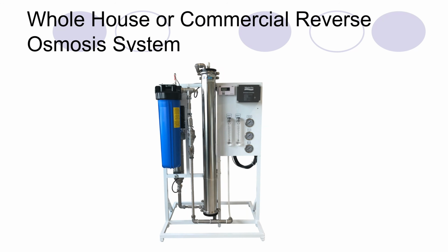And would it be an issue to put a larger gallon per day membrane than you actually need? Well, I'll give you an example. So I have a picture here, I think, yes, this one here. Okay, so this is a whole house reverse osmosis system. And this is actually the one that we have in our store here. So the one we have in our store is 4,800 gallons per day. And so you see that stainless steel cylinder that's up and down in the middle? That's a 2,400 gallon per day membrane. Our 4,800 gallon per day has 2 of those membranes. Our 9,600 has 4 of those membranes. So that's how you increase the production, is by adding more membranes. And I hope that answers your question.